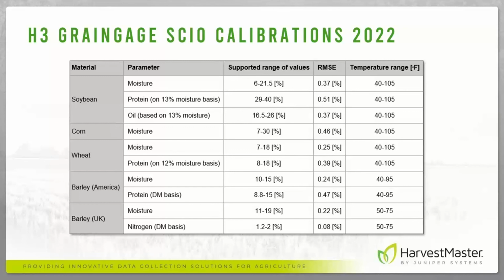Gregory said, issues with trash ending up in the NIR sampling vessel. I work with soybeans. Our plot samples can have sticks, stems, and pods in them. Yeah, that's a good question. In fact, we saw that too, and we have run some tests where we purposefully used a trashy sample and a clean sample. Specifically on wheat, we ran the dirty sample that had a lot of junk in it, and then we ran a clean sample. And we didn't see a very significant difference in the reading. There were times where if we had a big leaf or something from a corn stalk on there, that it gave some variation in the reading. But overall, we haven't seen really any problems with trash.